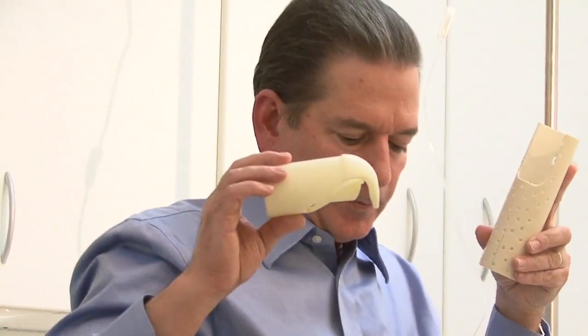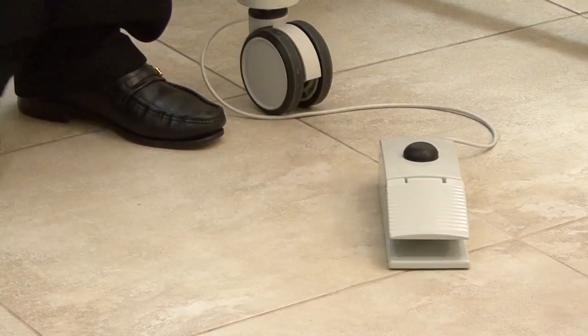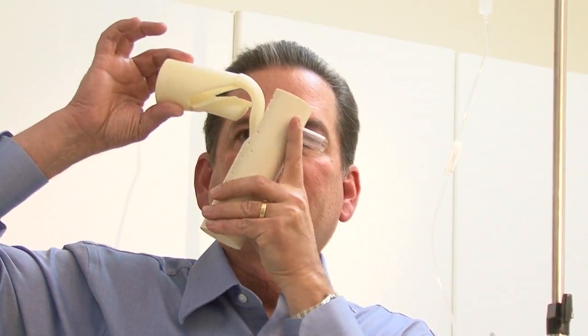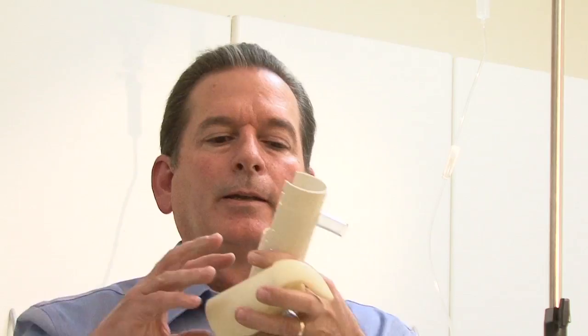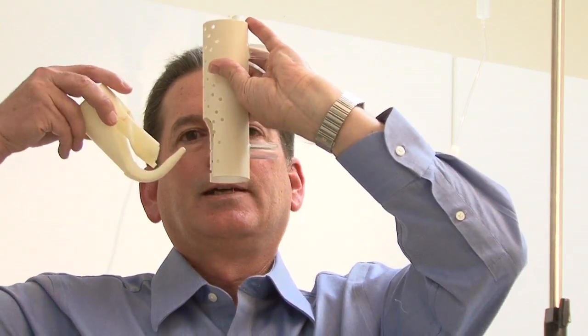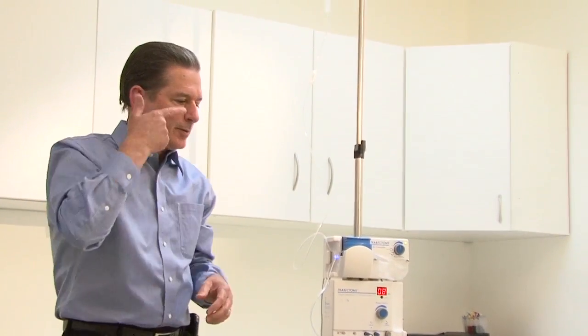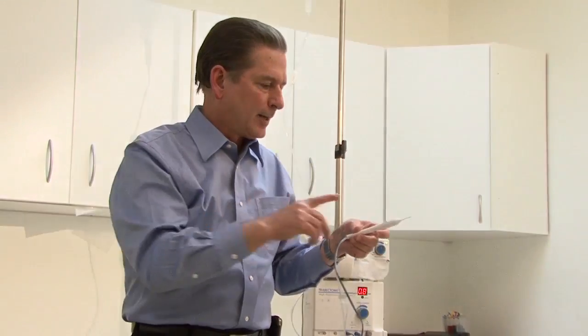Then you'll hear them go down on the foot pedal. And when you hear the tone, they're firing the electrosurgery and moving along Schlemm's canal. They'll come in from the incision and go one direction. And usually they can open up about 60 to 90 degrees in one direction. Then they'll come back to the center, reverse, start off where they left off, and typically extend. And we can usually do about 90 to 120 degrees of the opening of this trabecular meshwork in the nasal sector. And that's sufficient to expose a lot of these collector channels and reestablish the outflow in the eye. So once the ablation is completed, the surgeon will withdraw the handpiece from the eye.